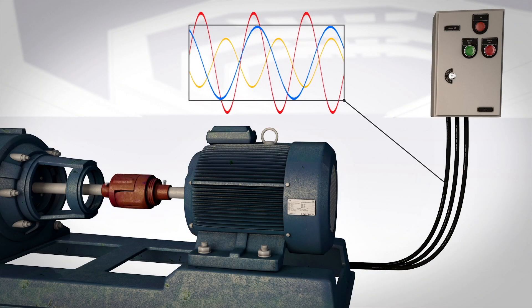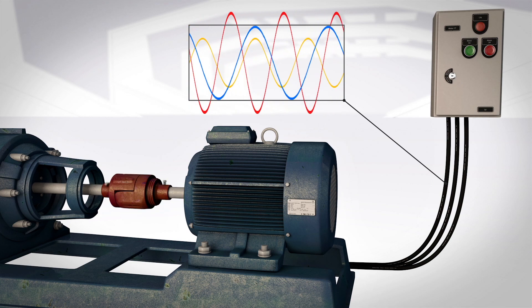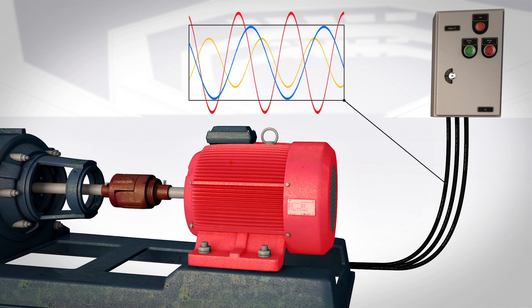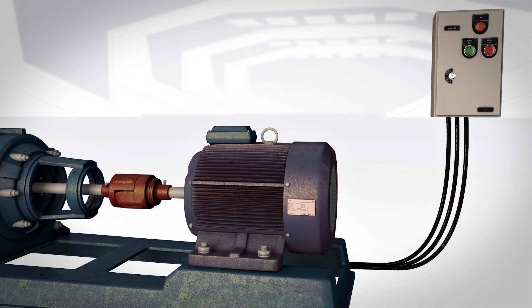Power quality issues, such as unbalance and harmonics, can cause motors to run hot, eventually stressing windings and accelerating failures. Motor failures lead to costly downtime, and the cost of waste associated with inefficient motors adds up.